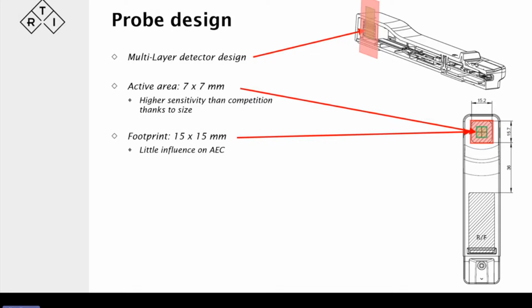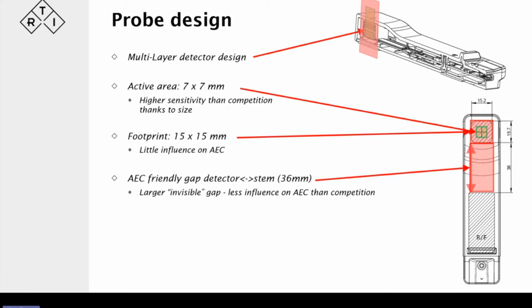Now there is a balance, of course, in fluoro applications. The bigger the size of the detector, the higher the sensitivity, so we need to balance it to have enough sensitivity for the low dose rate fluoro, some of the low dose fluoro applications, but still provide a little footprint in the beam. So we think we've found an optimum ratio between performance and size. We've provided an invisible gap between the detector itself and the electronics in the beam, so that we can place it and have as little influence as possible of the probe in the beam.